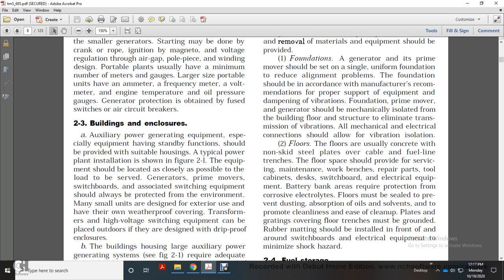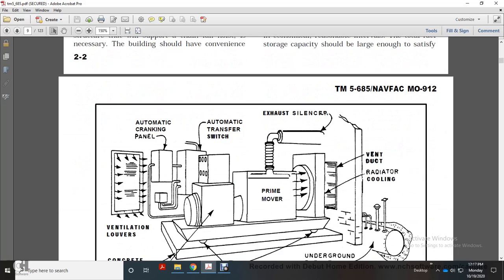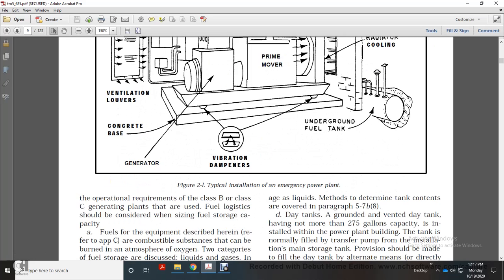Rubber matting should be installed in front of switchboards and electrical equipment to minimize shock hazards. Fuel storage: Fuel storage space should provide enough capacity to allow economical replenishment at reasonable intervals. The system includes automatic cranking, automatic transfer, exhaust silencer vents, radiator cooler, underground fuel tanks, vibration dampers, concrete base ventilation, and associated components.